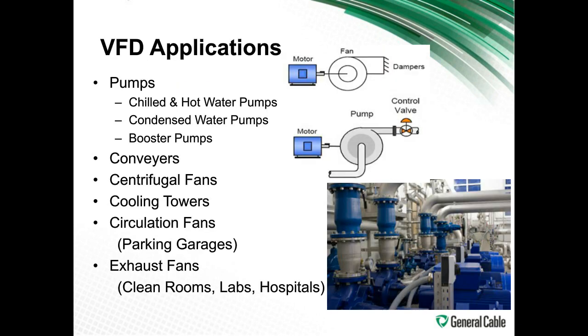These applications are multiple. You see them used for pumps, hot water pumps, condensed pumps, booster pumps, conveyors, fans, cooling towers, circulation fans, exhaust fans. I was just at a game recently, after the game, this was the Caps game, I went to my car in this crazy parking garage, and you have a lot of cars trying to leave at the same time, emitting the CO into the air. And the whole time I'm thinking, my God, this is not good. So that now you're seeing more circulation fans being used in parking garages, and they can be controlled with VFD drives, so they're not used constantly, but only when they're needed the most. So that's another really good application.